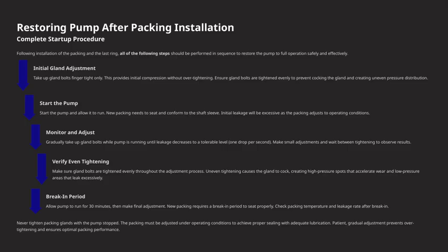Next, we start the pump and let it run. Remember, new packing needs some time to seat and conform to the shaft sleeve. During this initial period, expect some leakage. This is normal as the packing adjusts to the operating conditions. While the pump is running, monitor and gradually tighten the gland bolts. The goal is to reduce leakage to a tolerable level, typically about 1 drop per second.